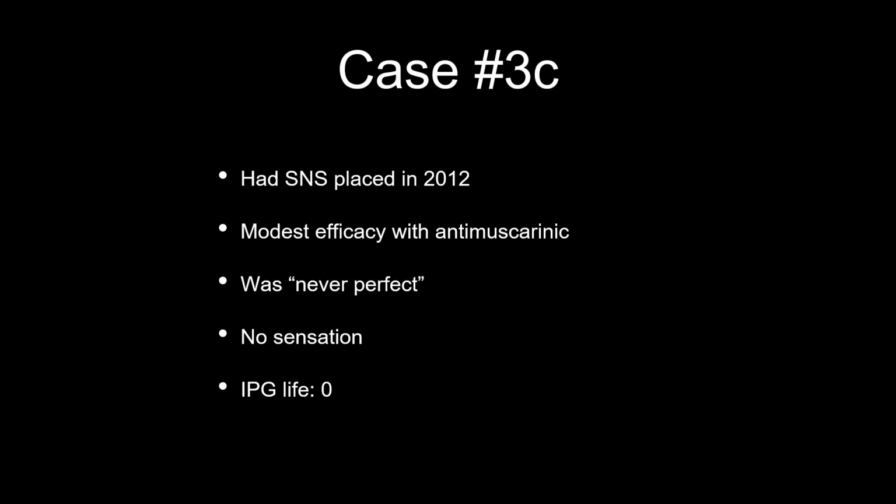Now, having said that, it's obviously not necessary for you to change the lead in somebody who's doing well and who doesn't need an MRI to an MRI compatible one. I have heard of people doing that, and I don't think that's a great thing to do, because you've got something that's working, number one. Number two, it's an operation they don't need.